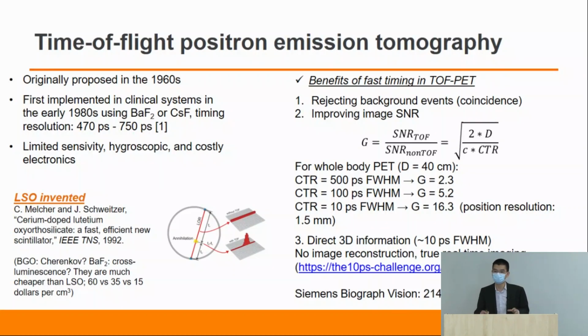This will give us a position resolution for the 511 keV gamma rays of about 1.5 millimeters. So this position resolution is comparable to the range uncertainty of positrons. And if we can have 10 picosecond time resolution, we can have direct 3D information. This means we do not need image reconstruction, and we will have a true real-time image. The overall benefit of time of flight is that it can reduce the dose and the imaging time for the patient. There are a few commercial time-of-flight PET systems on the market. Siemens has the best one in terms of time resolution, about 214 picoseconds full width at half maximum at the system level.